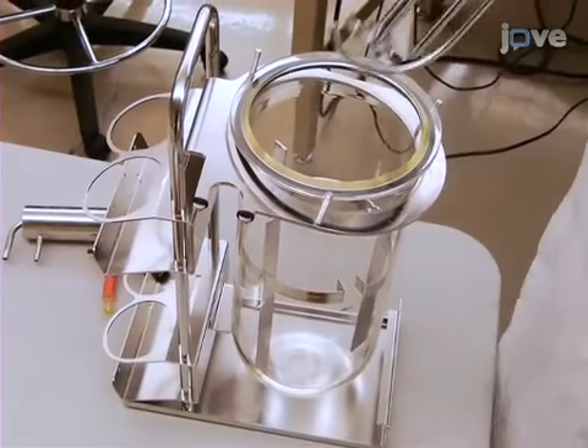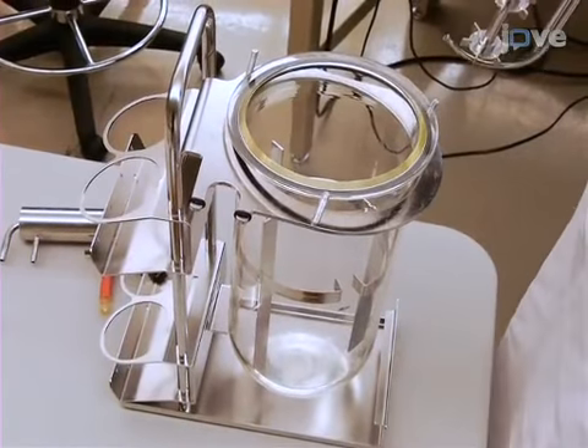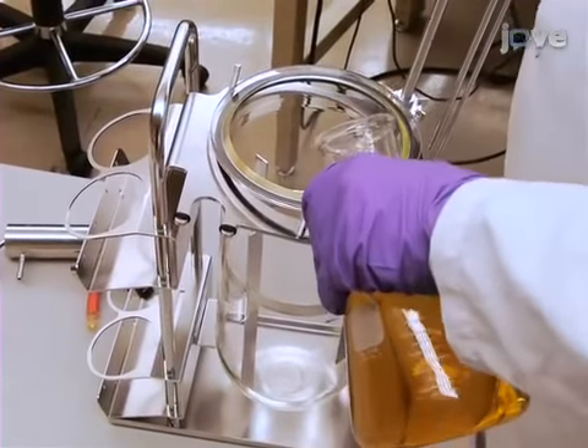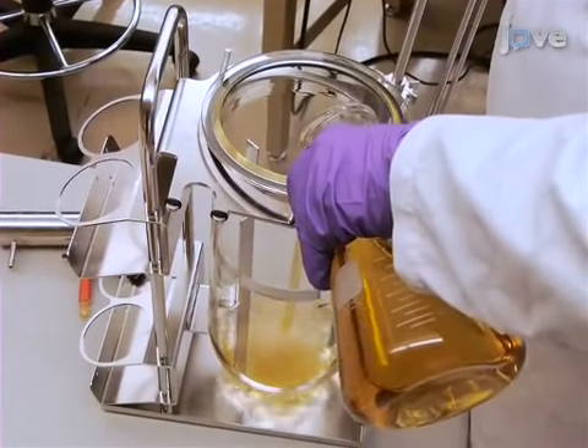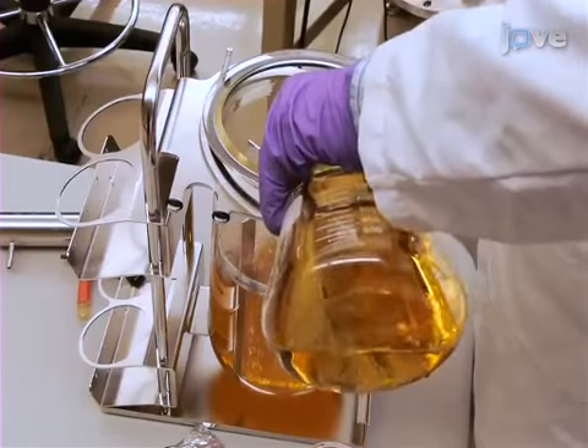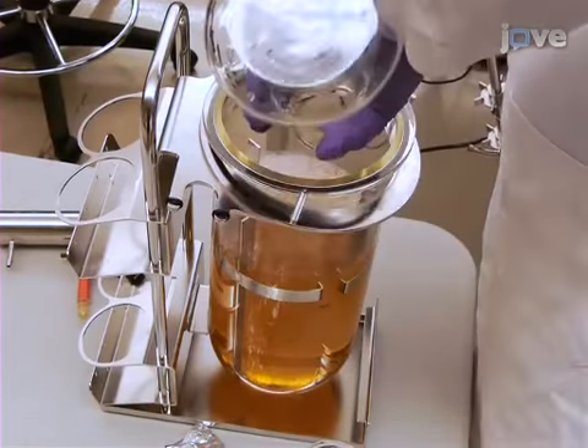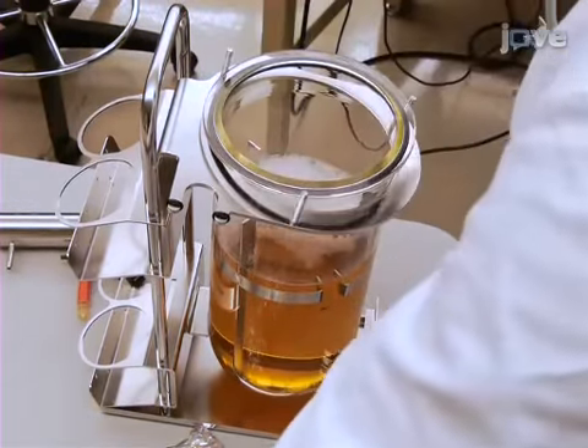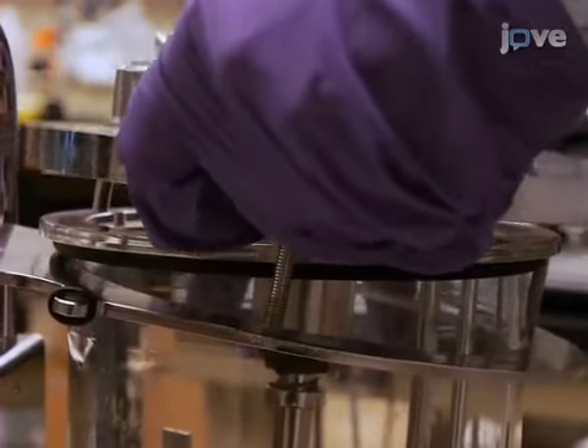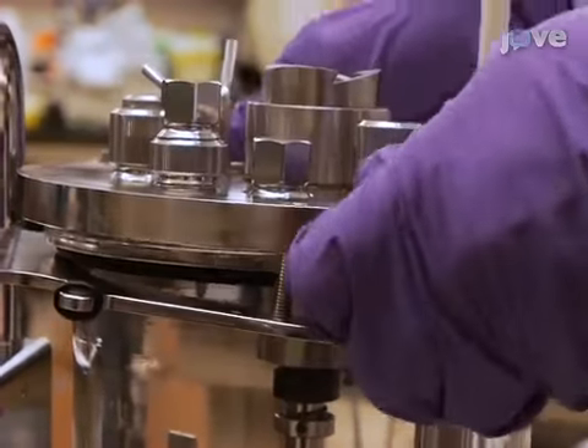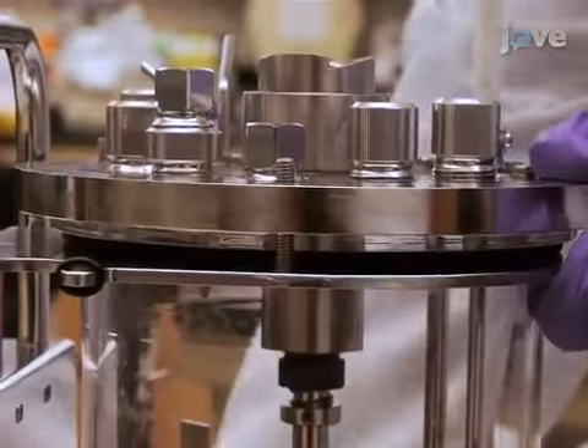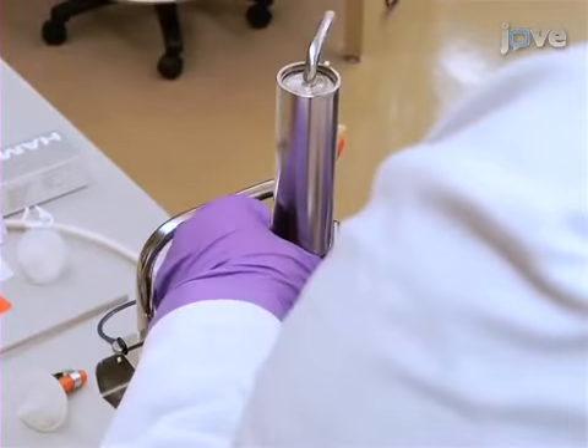To begin, add bacterial medium that is not heat labile to the clean vessel. Only add until maximum working volume is reached, which is 3.3 liters for a 5-liter total volume vessel. Mount the vessel headplate, ensuring that the O-ring seal is properly seated. Install the exhaust gas condenser.